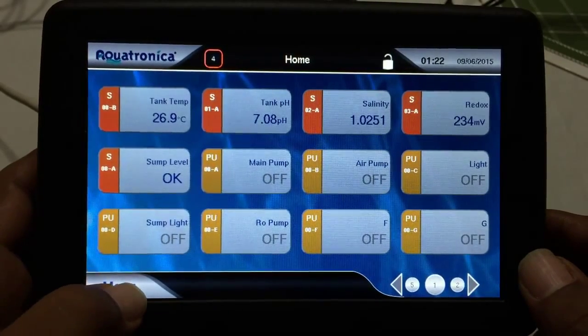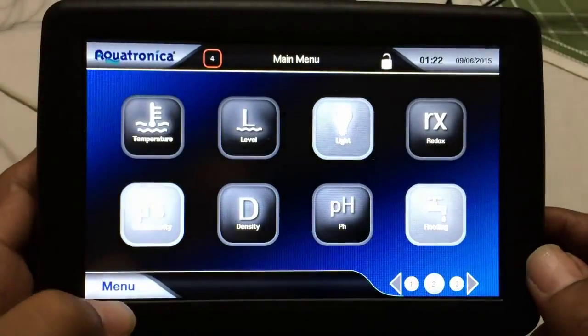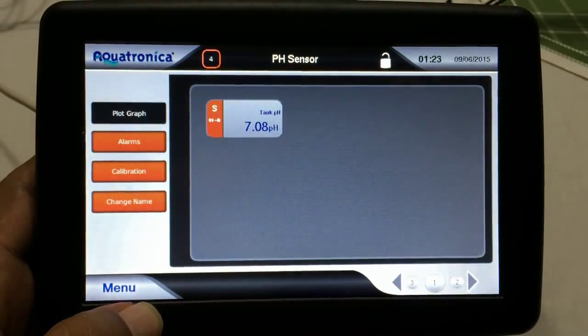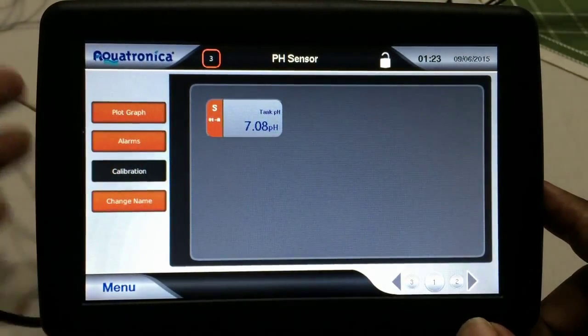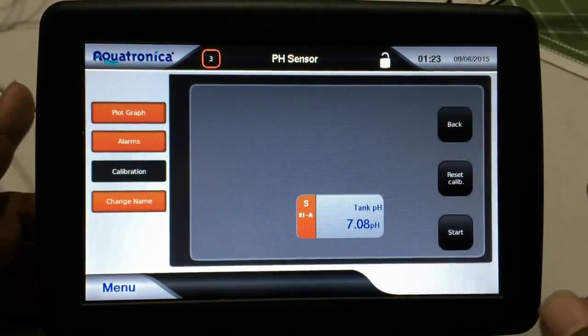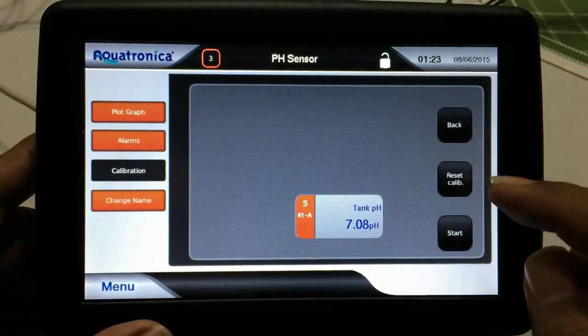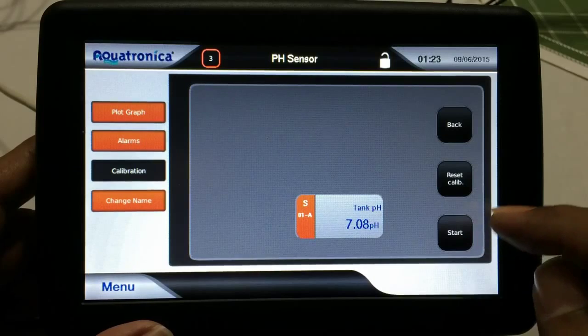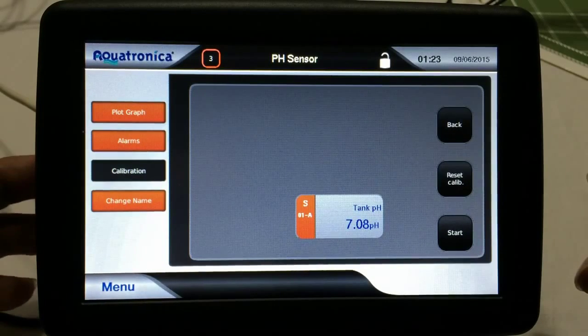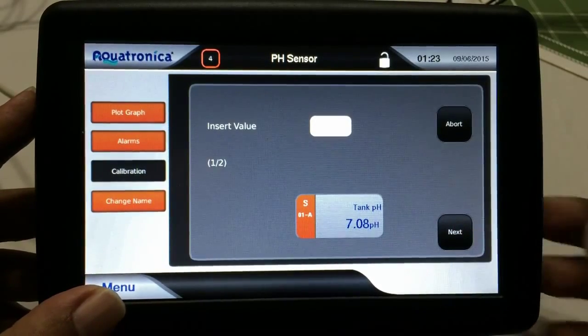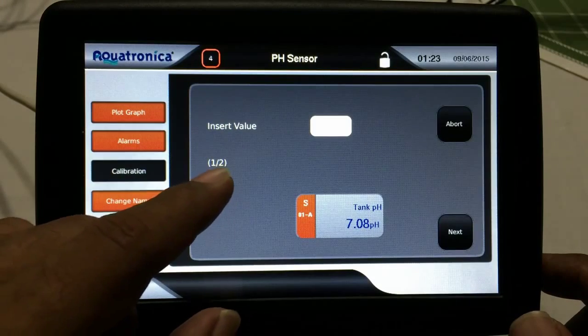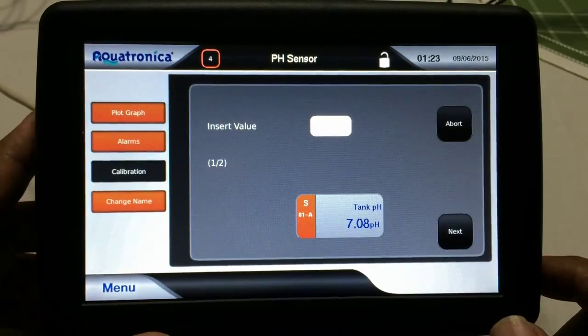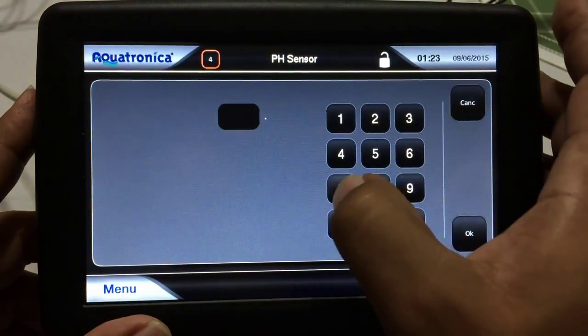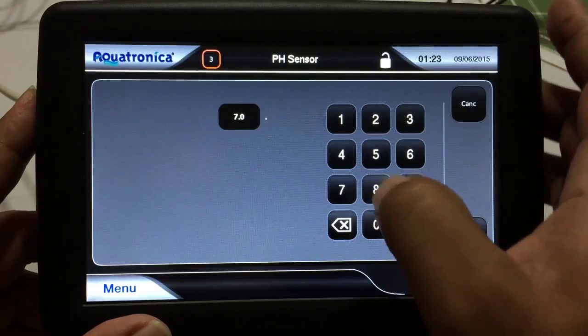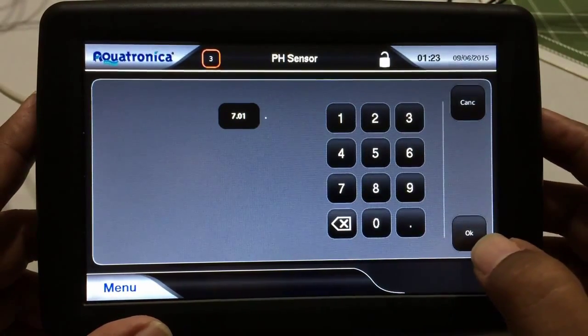So the first thing I'm going to do is press menu, and I'm going to go into the pH, and I'm going to go to calibration, and I'm going to pick the one probe I have, and here you have back, reset calibration, and start. Well, I guess reset calibration is if you mess up and you need to start all over again. So I'm going to press start, and it wants the first value, and you can see here it says 1 of 2 because, as I said, there are 2 values you need when you calibrate any pH probe. So I'm going to insert the first value, and it's 7.01. Alright, and I'm going to press OK.